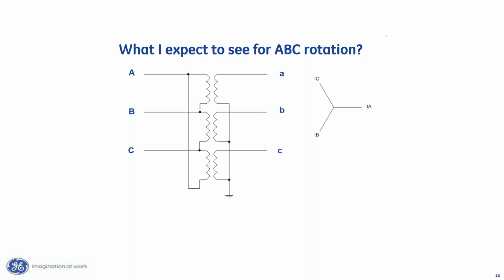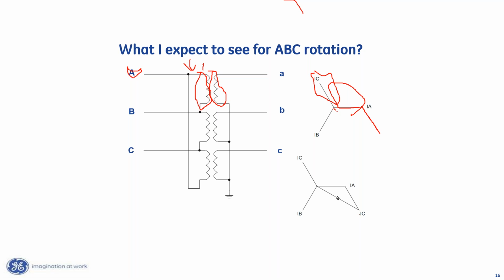Now, if I look at little a, what do I expect to see on little a? Well, little a is a combination of A and C, right? Because of this dot right here, what is on this winding right here is exactly in phase with what's on that winding right there. But the problem is what's on that winding right here is not actually A phase. It's A minus what I've got on C here. So to figure out what I've got on A, I take this A, and I'll superimpose C onto A, but it's minus C. So C's sitting right down here, and I get little a, right?